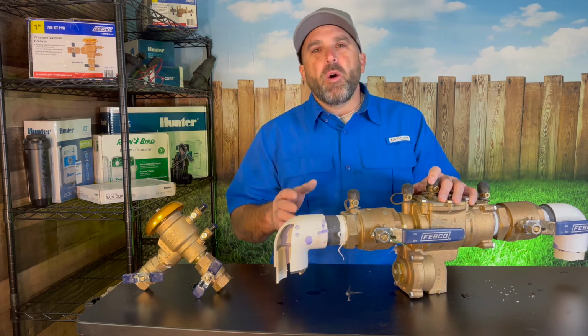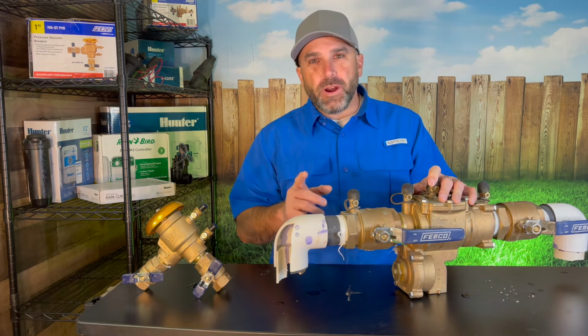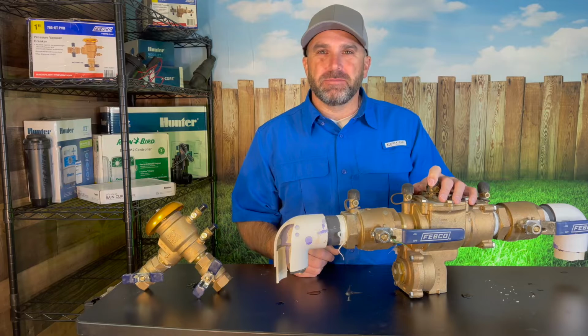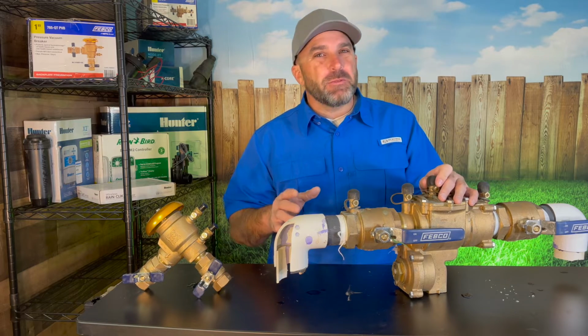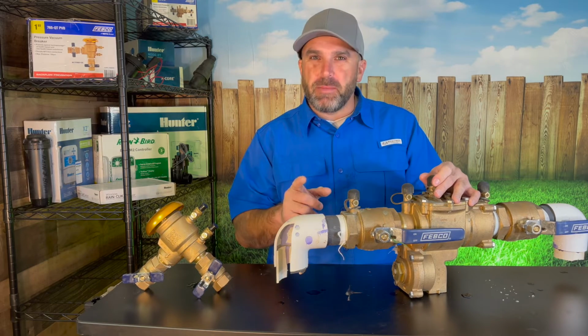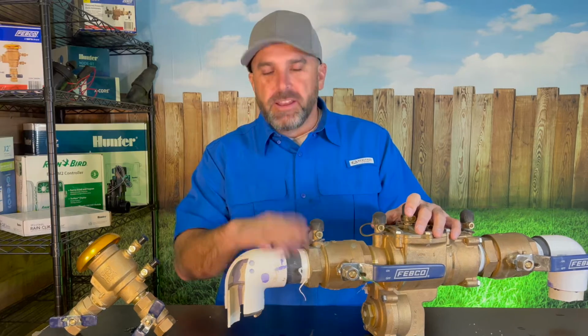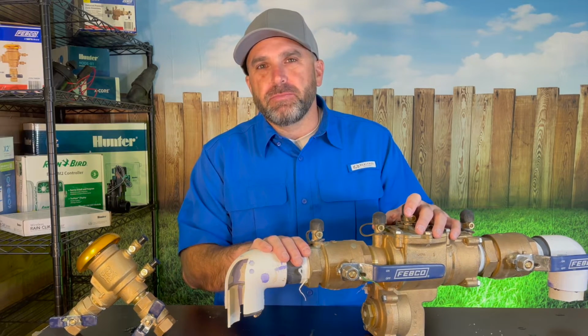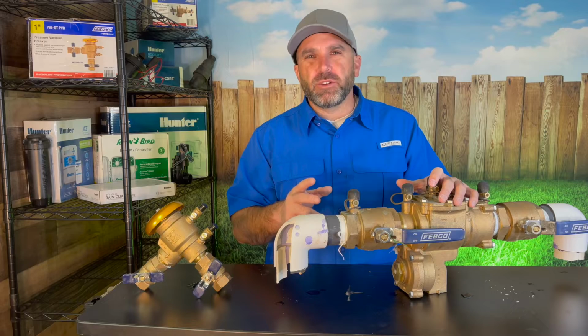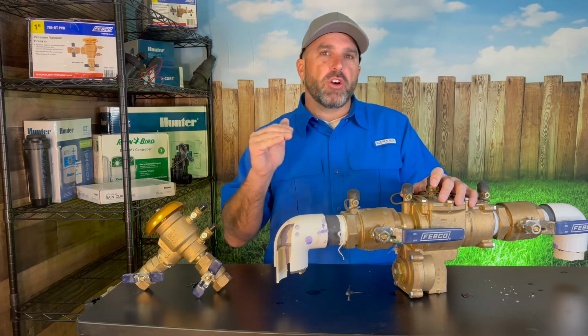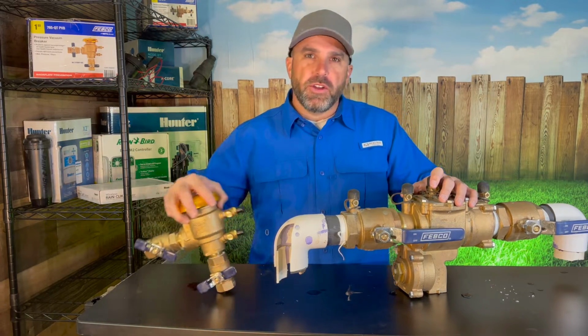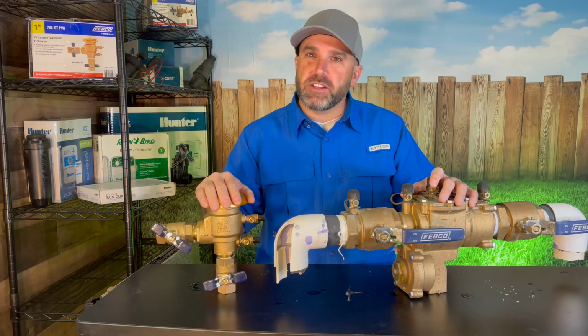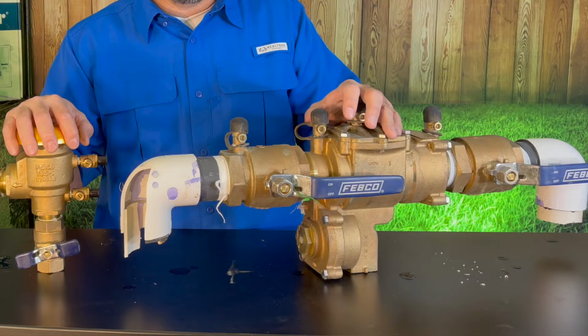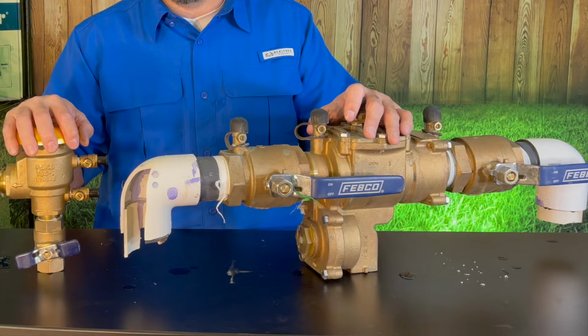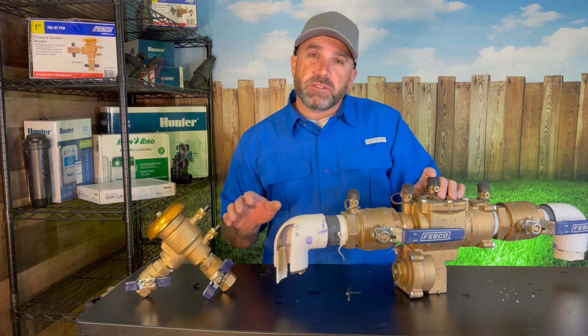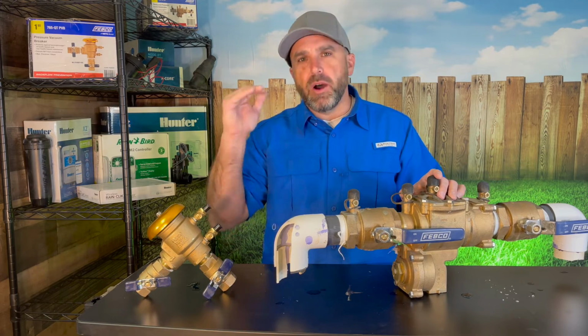Today I'm going to talk to you about why it's important to winterize the backflow device on your sprinkler system. When it starts getting cold outside, one of the things you want to make sure you think about is winterizing the backflow device on your sprinkler system. Now, two of the most common backflow devices that are installed above grade are what's called a PVB, or pressure vacuum breaker, or an RPZ, a reduced pressure zone backflow device. These two types of backflow devices are to be installed above grade.